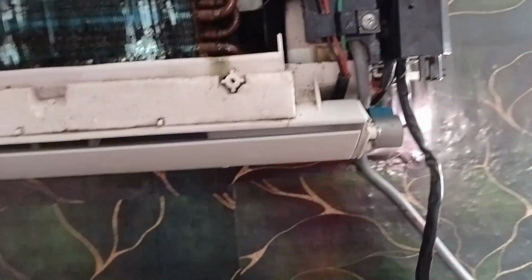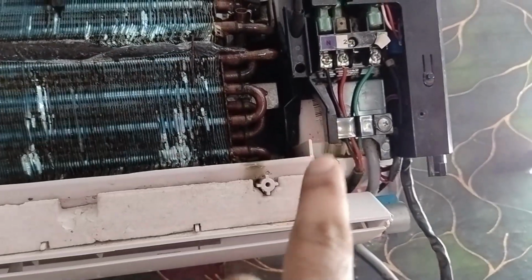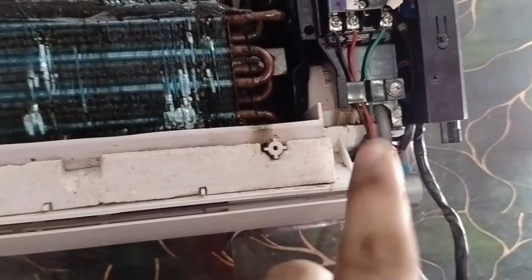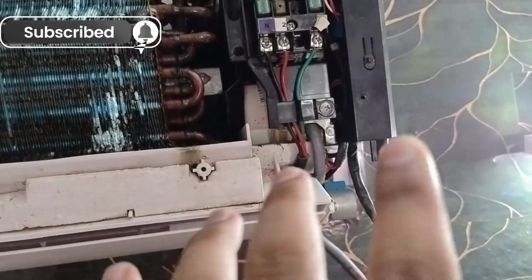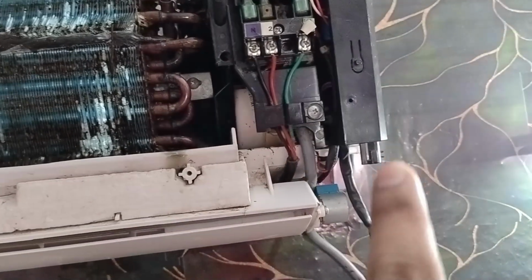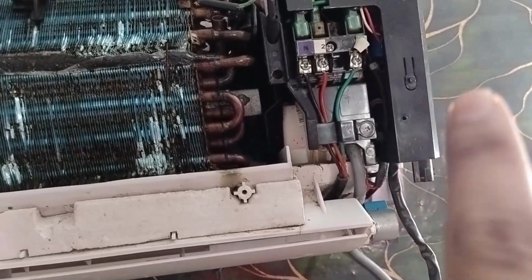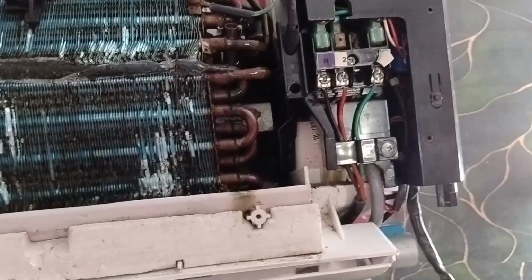So now the point is the blower motor could be bad, or the connections could be bad, and the important thing is the feedback wire that must be checked, of course. So let's see what's the problem in this case.